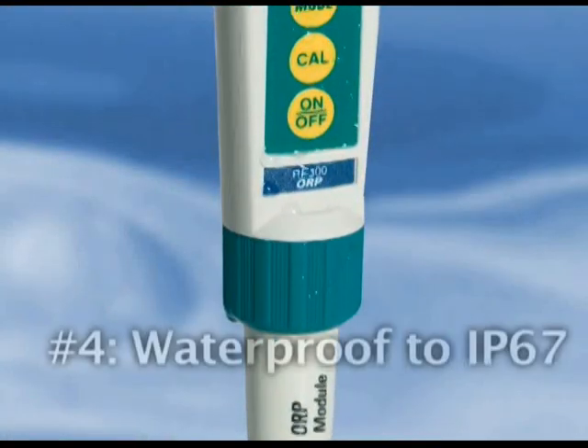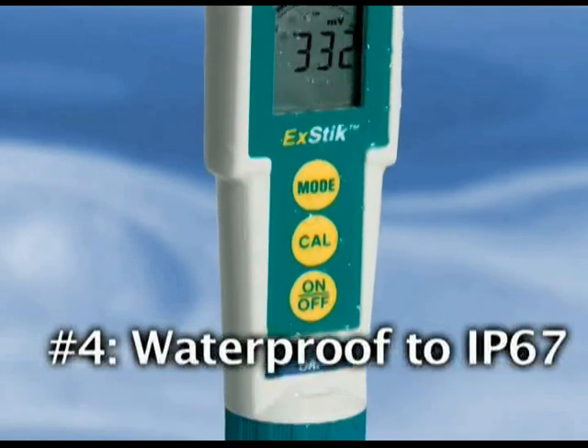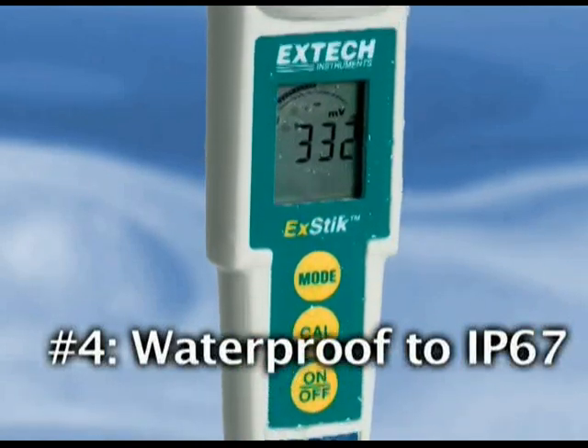4. The ExStik ORP meter is completely waterproof, meeting the standard of IP67. This assures safe and accurate measurements even during extreme wet conditions. The meter also floats when dropped in water.